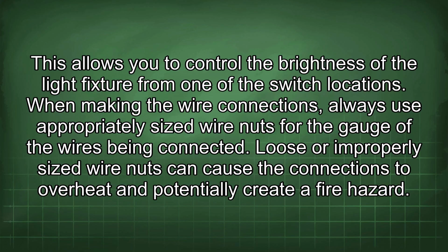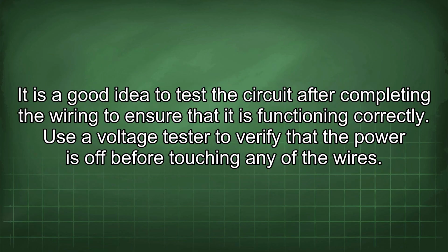When making the wire connections, always use appropriately sized wire nuts for the gauge of the wires being connected. Loose or improperly sized wire nuts can cause the connections to overheat and potentially create a fire hazard. It is a good idea to test the circuit after completing the wiring to ensure that it is functioning correctly. Use a voltage tester to verify that the power is off before touching any of the wires.